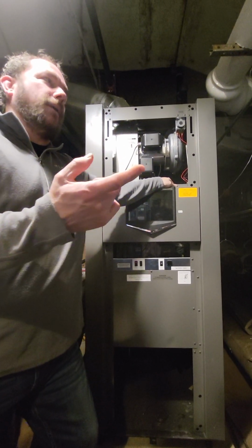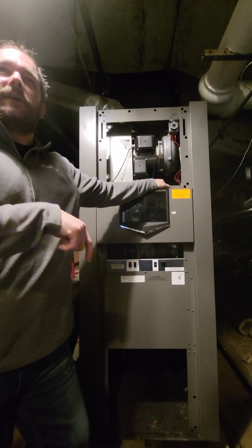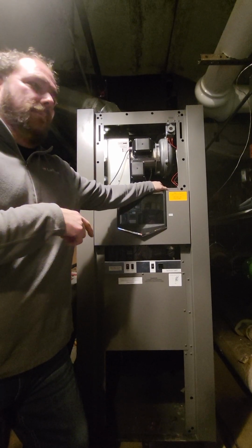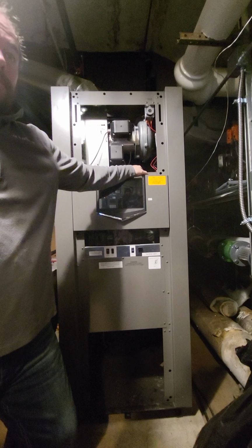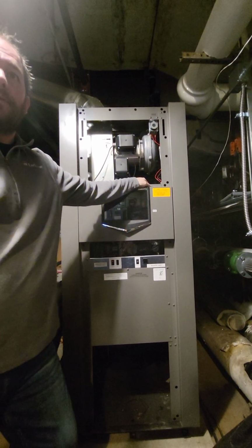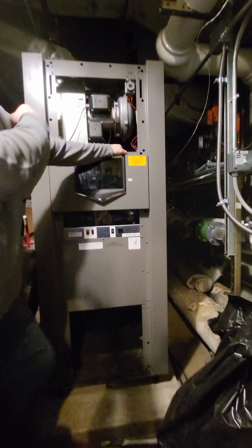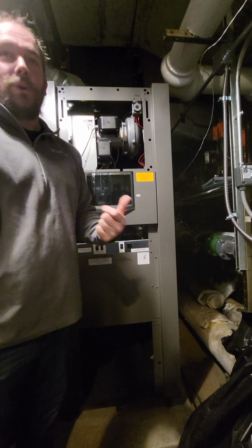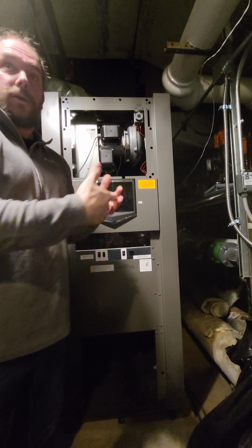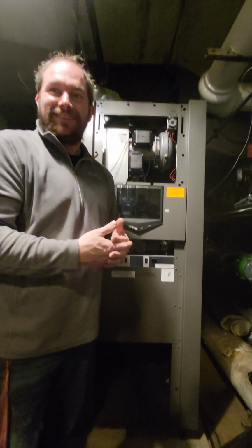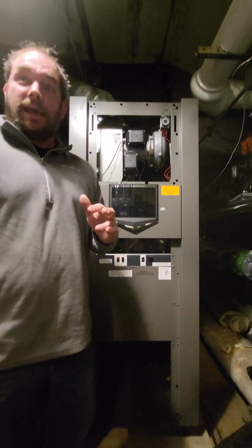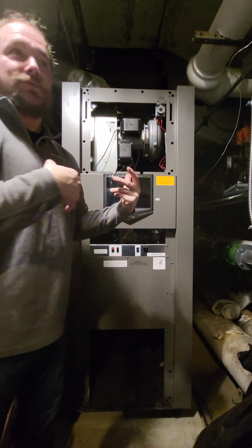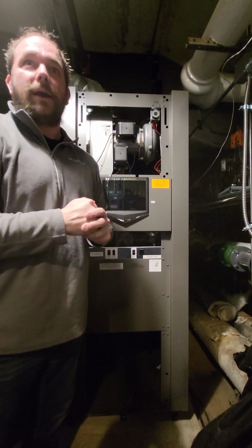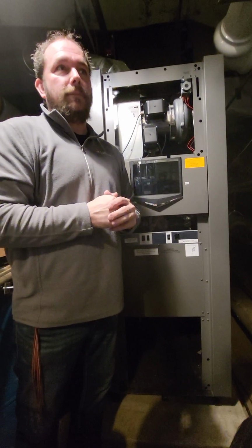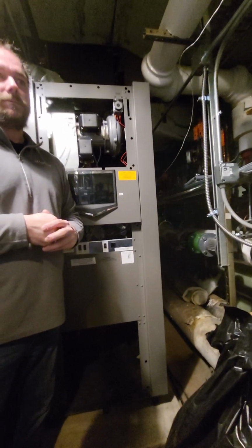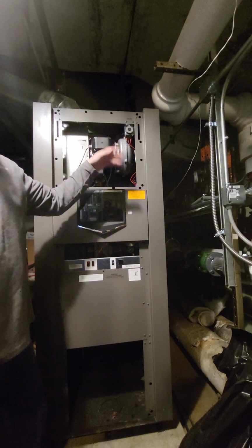I think the water quality guy was here the day that I started this up, if I'm not mistaken. This is the same water that's in your campus loop, right? Yes, and that water is maintained quality-wise. Okay. I would say look at the manual, and as long as it's a stainless steel heat exchanger. I don't know what the rest of the loop is, but make sure our water quality numbers jive with what you're doing. Good equipment here, a lot of stainless steel. All right, so if your main equipment is stainless steel heat exchangers, you're probably treating for the same range that we would want anyway. So, just something to look at. Water quality is maintained by an outside contractor, so it should be good. Gotcha. Yeah, water quality is probably one of the biggest problems we see nowadays.